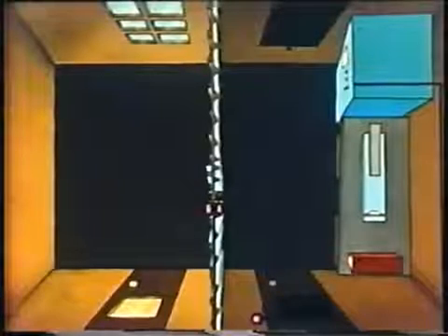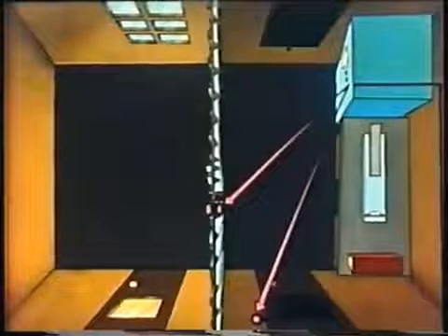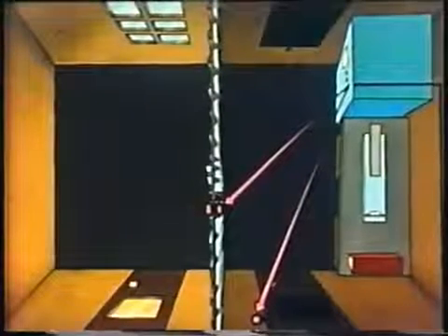The laser system should be isolated from any other activity in the room with a safe partition, such as a blackout curtain or folding screen. All windows and door windows should have blackout curtains or some other absorbent material. Safety interlocks should be provided for all doors, the primary entrance and the secondary entrance, such as the isolating screen.